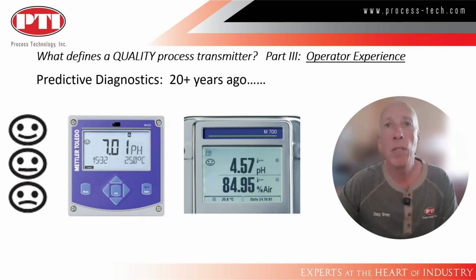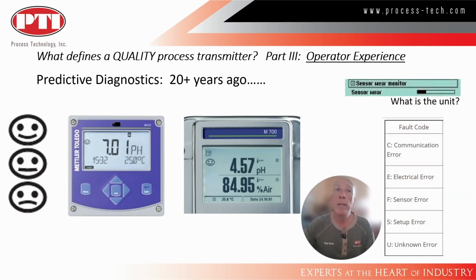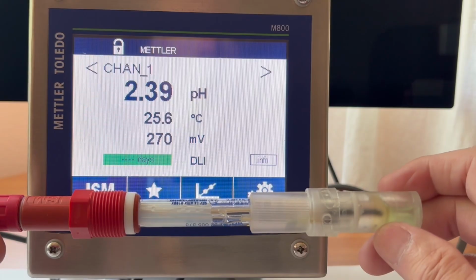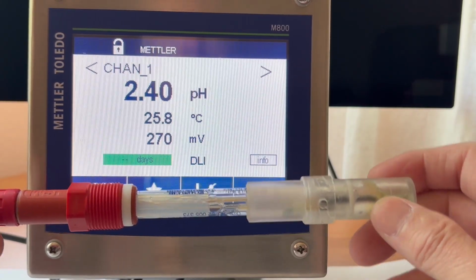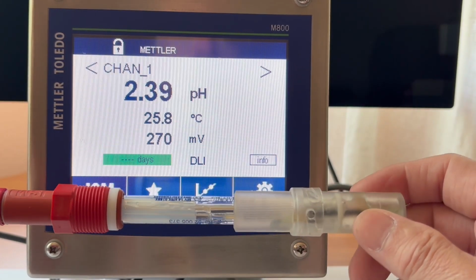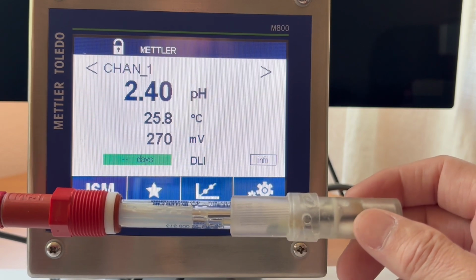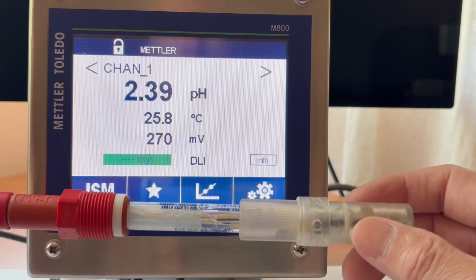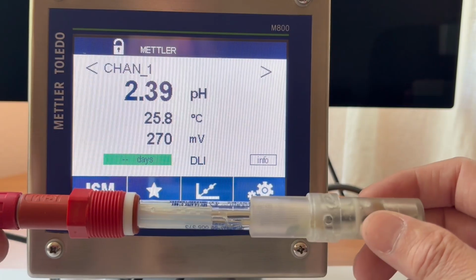However, the Mettler team realized this wasn't addressing the operator's needs, which is, when does the sensor need to be cleaned and calibrated? And more importantly, how much longer will this sensor last? Not as some percent in a wear monitor or a letter code you have to interpret. The ISM predictive diagnostics that Mettler-Toledo provides on their sensors is extremely powerful. It literally is reading out in terms of numbers of days, in terms of what actions need to be taken.